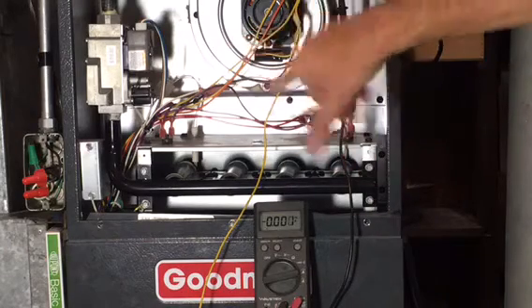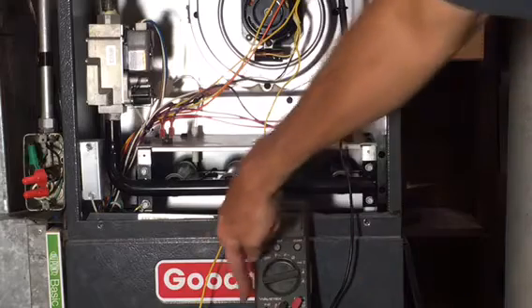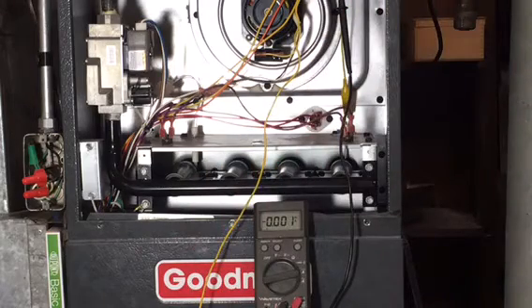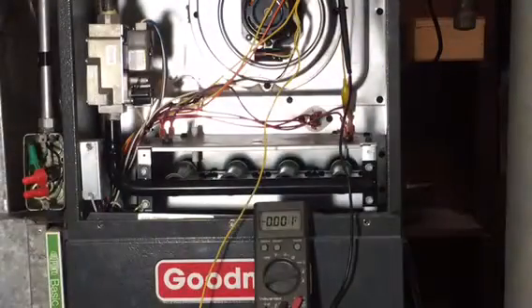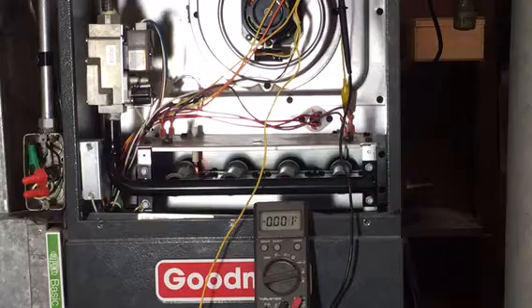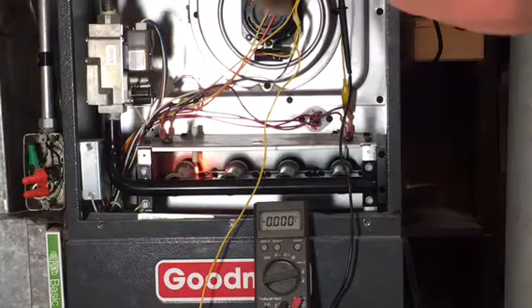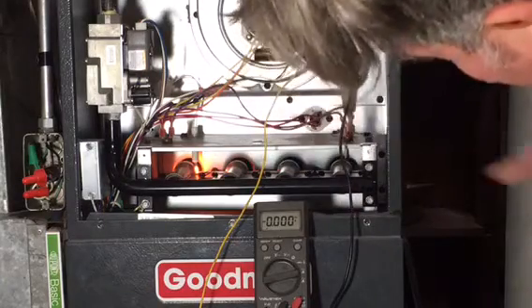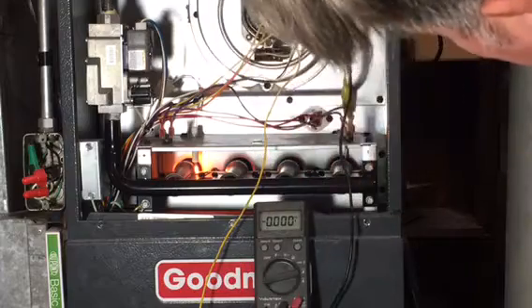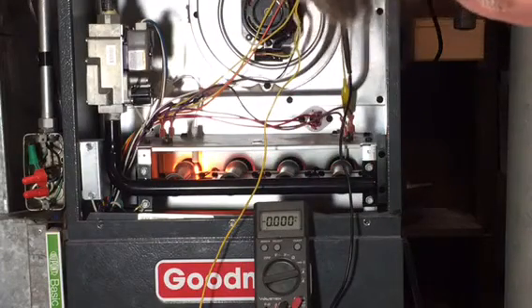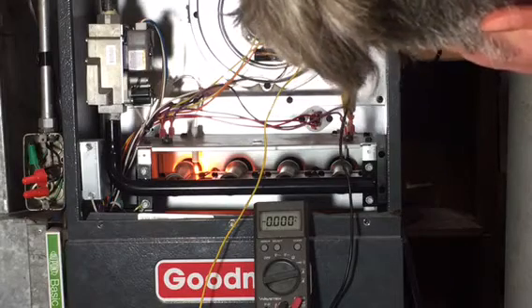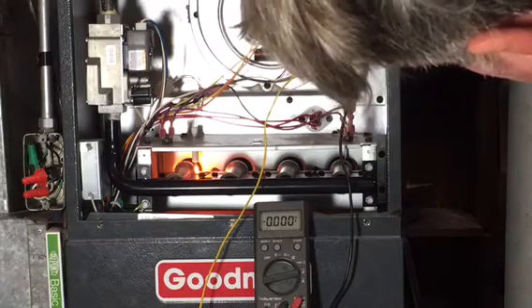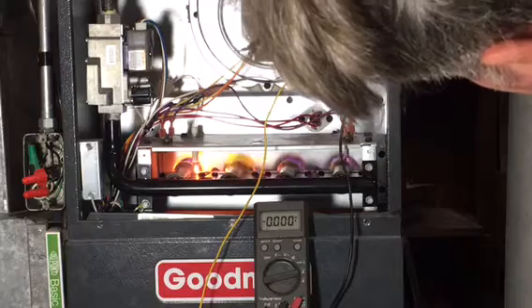The system is powered up. It's giving me the steady red light, which you can see through this hole. I'm going to run up and boost the thermostat and give it a call for heat, and we'll see what happens. Okay, got a call for heat. The induced fan blower is going. The igniter is going in here, you can see it. And the gas, it's probably got some air in this part of the pipe. It takes a little while to ignite. It should come on here hopefully in a second or two. There she goes.